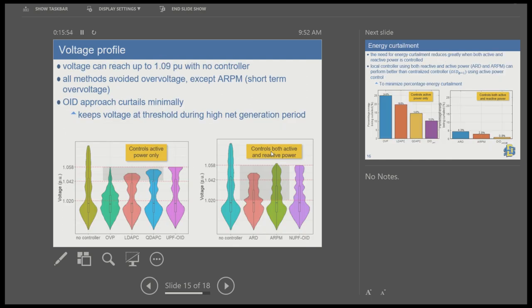Looking at the voltage profile for different inverter control approaches: without any controller, voltage can go up to 1.09 per unit. The threshold voltage limit is 1.058 per unit, and we want to keep voltage below this. Every control method can maintain voltage below 1.058 except for ARPM, because ARPM must first sense whether overvoltage has occurred, and it takes a certain time to control the voltage back below 1.058 — hence some transient overvoltage is observed with ARPM.